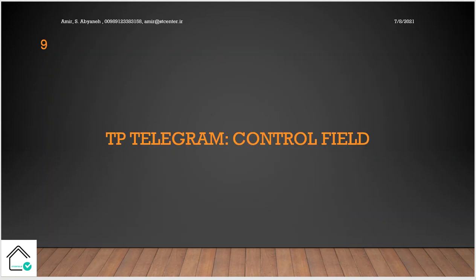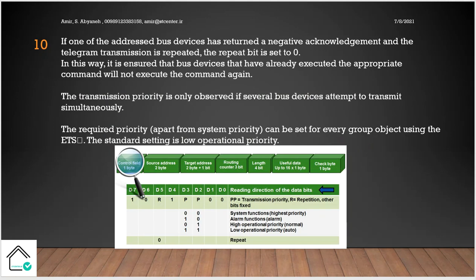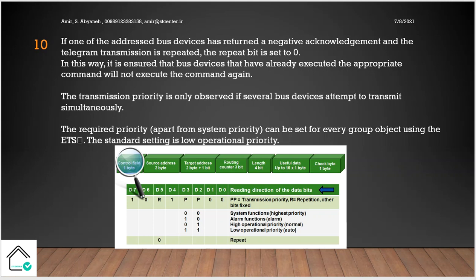So you remember we have the control field, some part of the telegram mechanics. We want to talk about it. What is the control field? So if one of the addressed bus devices has returned a negative acknowledgement and the telegram transmission is repeated, the repeat bit is set to zero. In this way it is ensured that the bus devices that have already executed the appropriate command will not execute the command again.